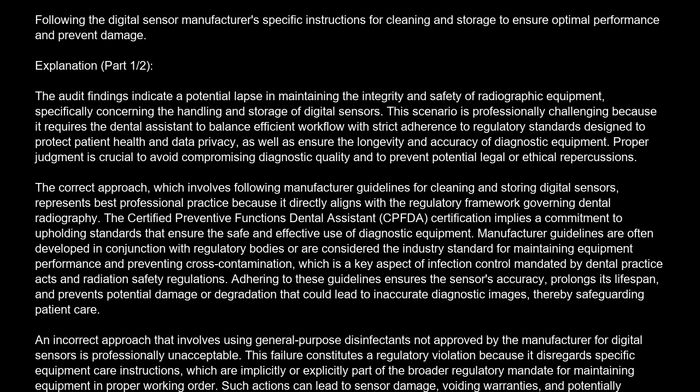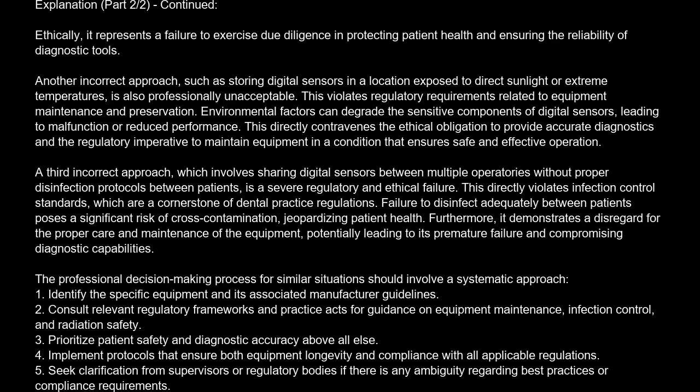An incorrect approach that involves using general-purpose disinfectants not approved by the manufacturer for digital sensors is professionally unacceptable. This failure constitutes a regulatory violation because it disregards specific equipment care instructions, which are implicitly or explicitly part of the broader regulatory mandate for maintaining equipment in proper working order. Such actions can lead to sensor damage, voiding warranties, and potentially compromising image quality, which directly impacts diagnostic accuracy and patient care.